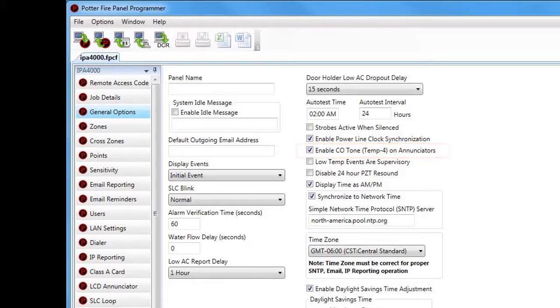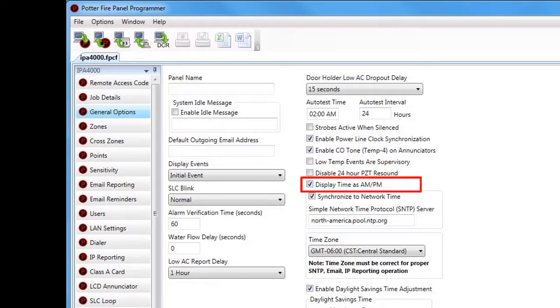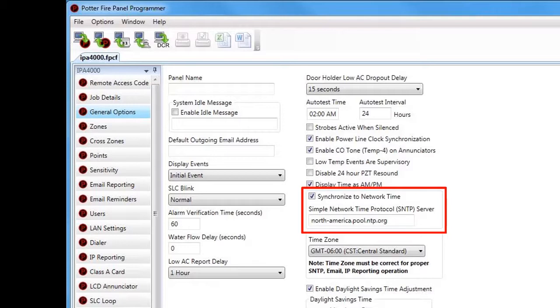Next is Low Temp Events Are Supervisories. When this box is checked, any heat detector designated for low temp via the Points section will annunciate a supervisory signal at the fire alarm control panel rather than a trouble signal when a low temperature event occurs. Next is Disable 24-Hour PZT Resound — when checked, this prevents the sounder on the annunciators from resounding after 24 hours when an off-normal condition remains on the system. Next is Display Time as AM/PM, which is checked by default; unchecking it will display time in 24-hour format on the panel and remote annunciators.